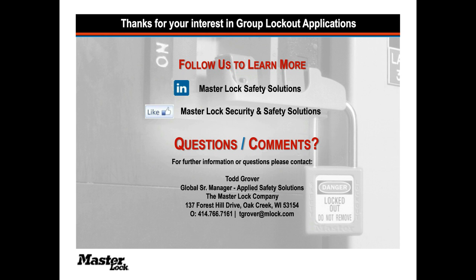That's a demonstration of a responsible system where what I want to know as I'm joining a lockout like this is that there's been primary and secondary verification of effective lockout. And then I make my own decision. Do I trust that? Or do I go check it for myself? But OSHA does understand it is a compliant practice, as long as that testing and verification is done, that each worker does not have to do their own.